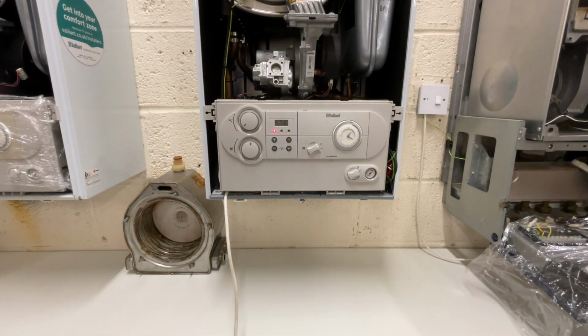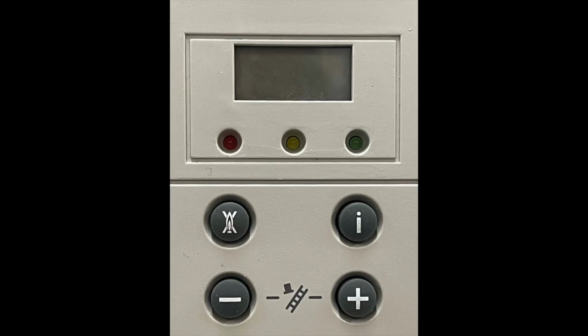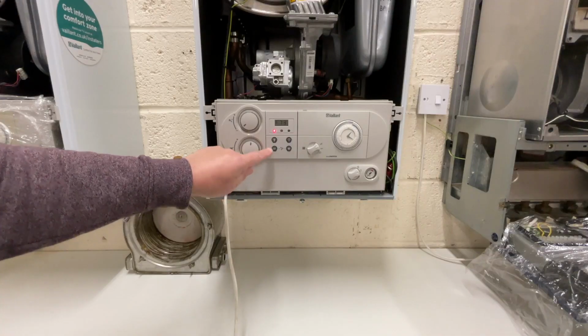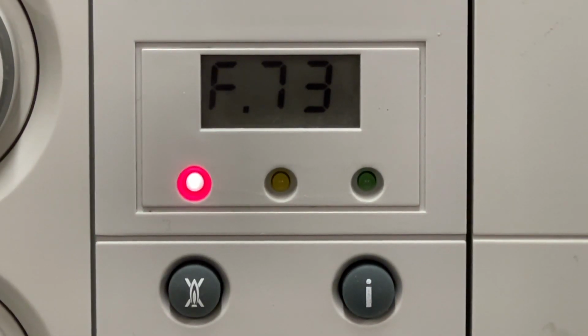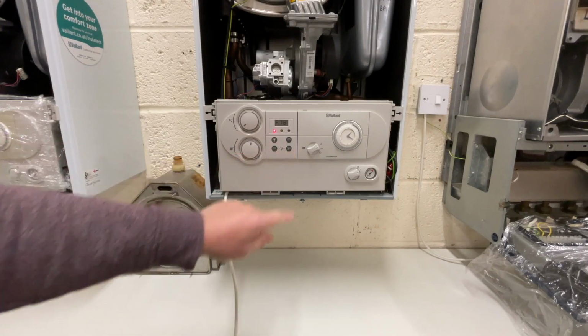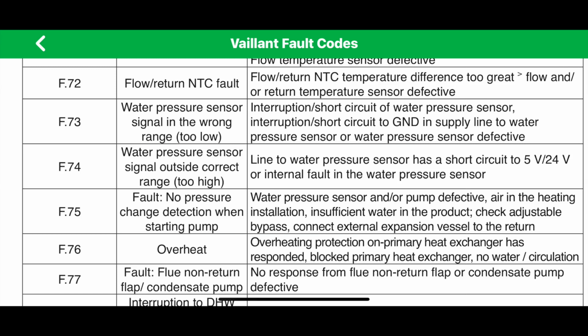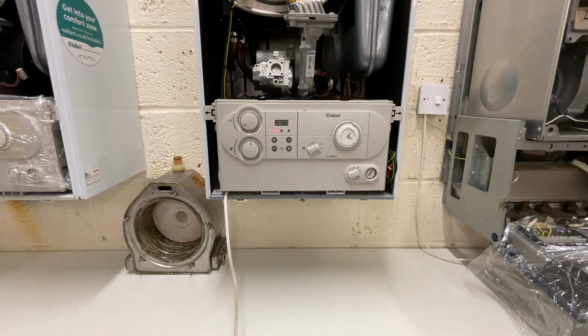To access the fault codes on this grey panel, we press the input information button and the minus button together, and as you can see here, it's scrolling and 76. We could also interact by pressing the plus button and then making note of all the fault codes. So if we look at 73, it tells us in the green book or the app, it's a water pressure sensor signal. It's in the wrong range because we've got no water in the boiler and it's picking this up. But it could also be that the boiler has got so much sludge that as soon as the pump kicks in, the water pressure sensor has not noticed it because it's blocked up, and therefore it's going to give us an error code that it's faulty.